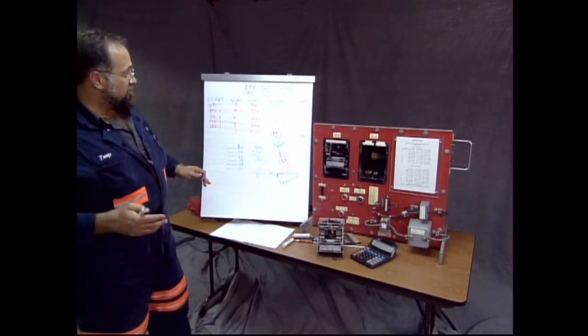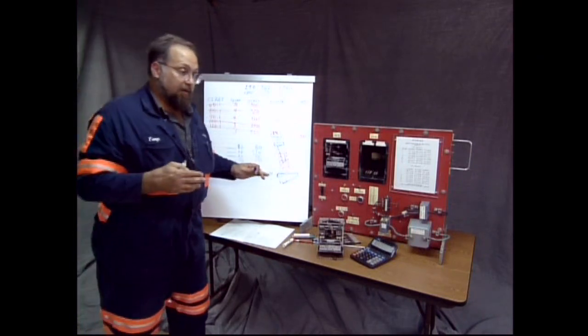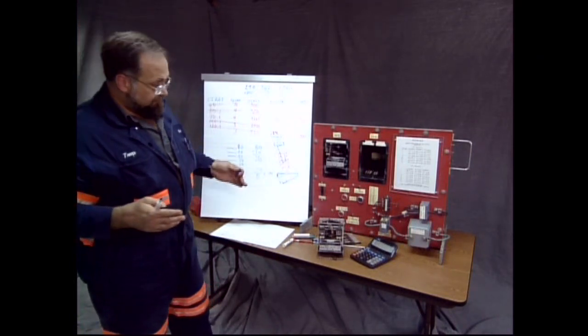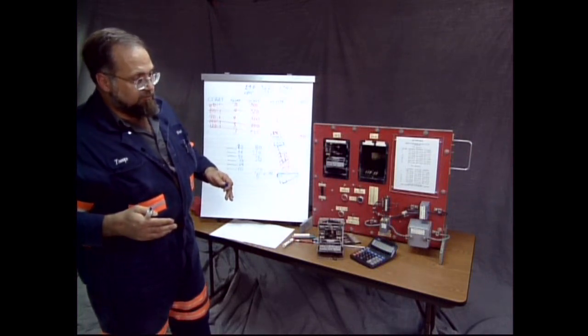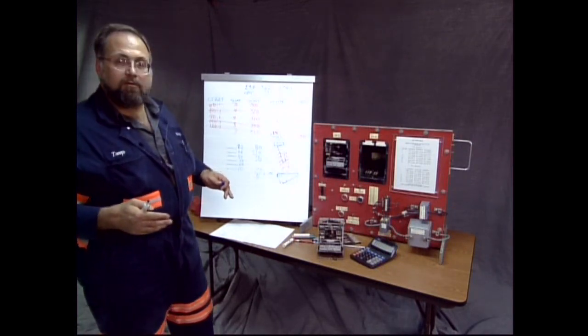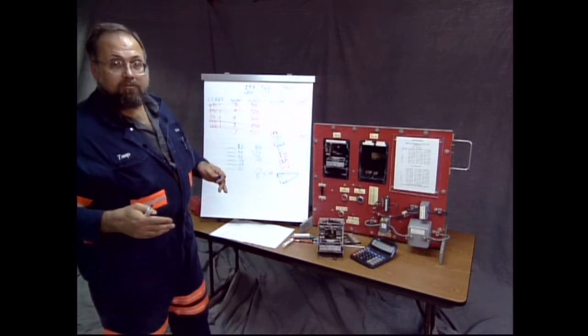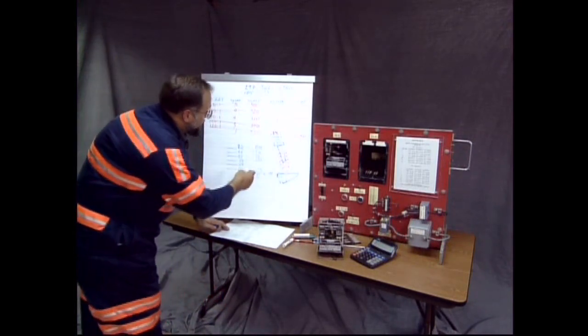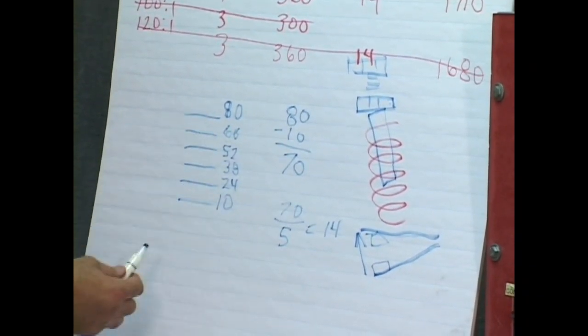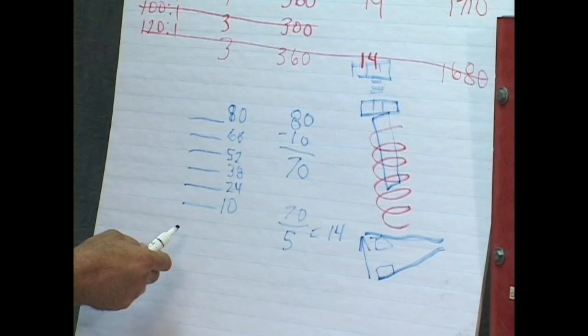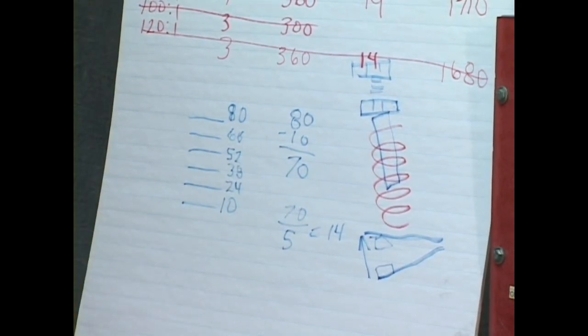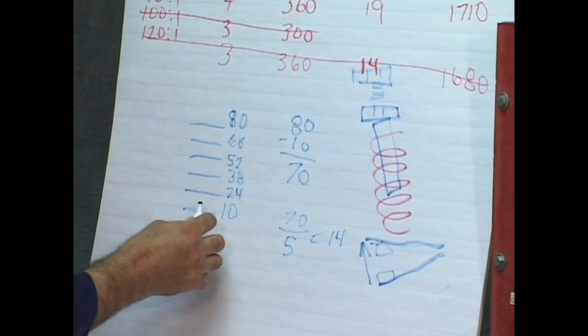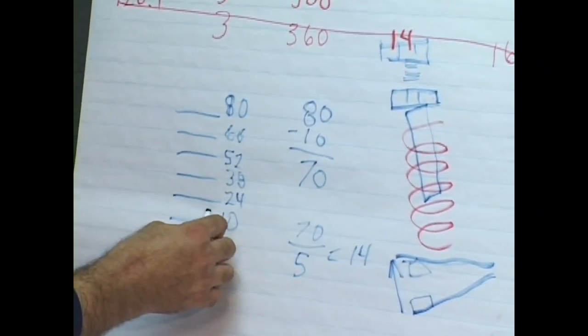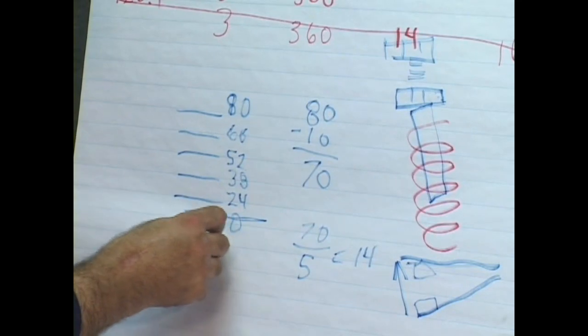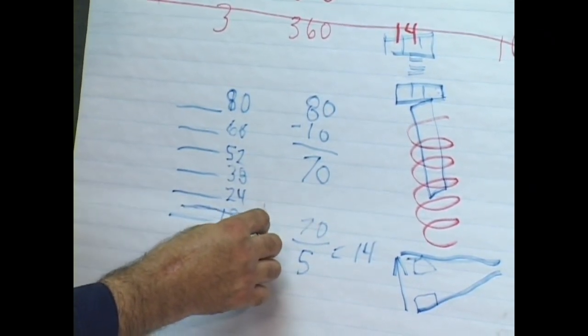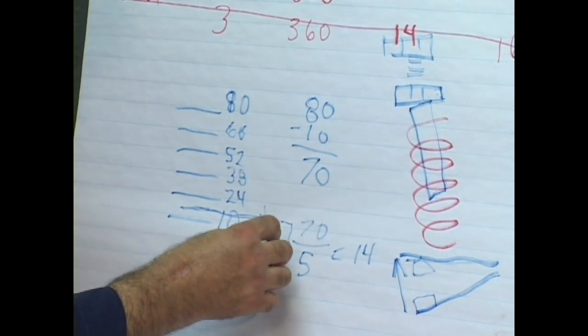You don't want to try to set. I've heard of people counting threads to adjust up and trying to adjust to a fraction of a core setting. Those are very difficult judgments to make, I'd say. If we were going to set it at 19, you have 24 and 10, a 14 span between them. 19 is just a little more than half that adjustment. I wouldn't challenge that half. I'd choose a point about half the thickness of a bolt head above 10, and I would adjust the top of my bolt to that point.